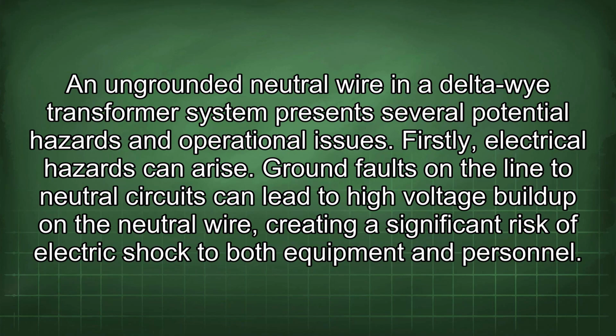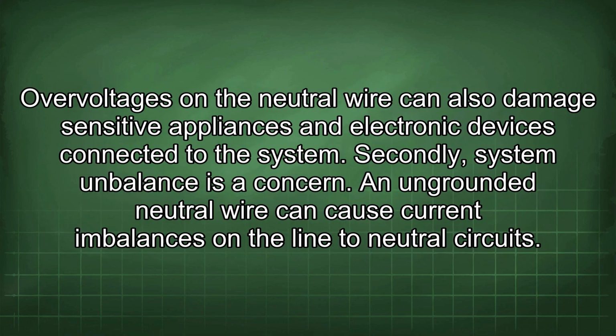An ungrounded neutral wire in a delta-wye transformer system presents several potential hazards and operational issues. Firstly, electrical hazards can arise. Ground faults on the line to neutral circuits can lead to high voltage buildup on the neutral wire, creating a significant risk of electric shock to both equipment and personnel. Overvoltages on the neutral wire can also damage sensitive appliances and electronic devices connected to the system.